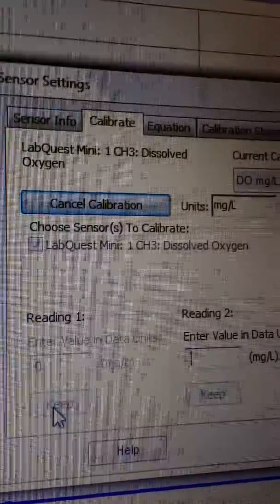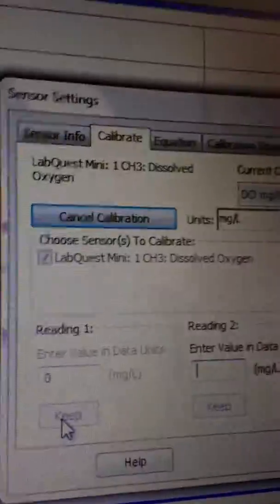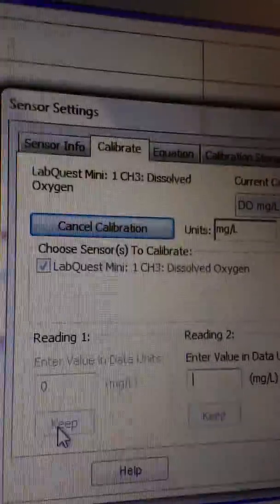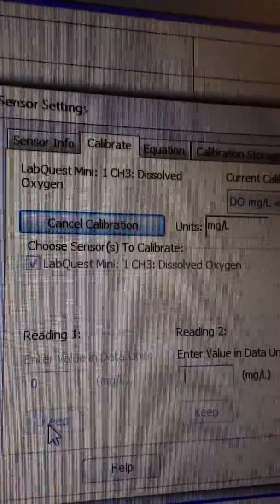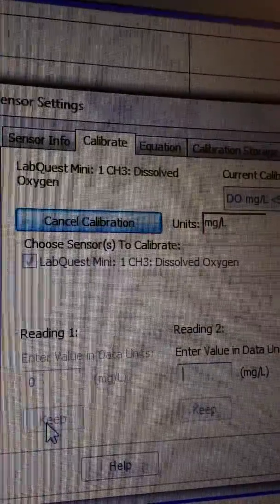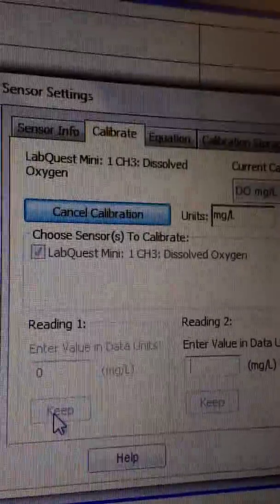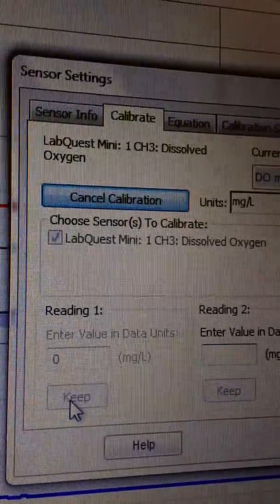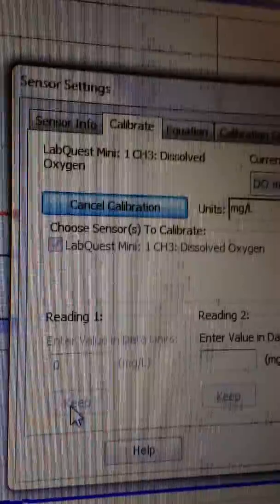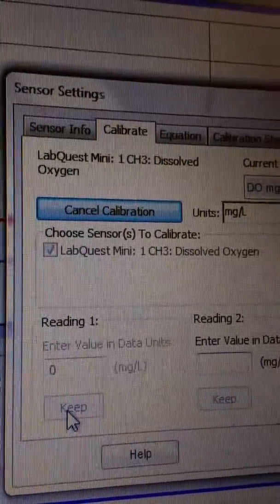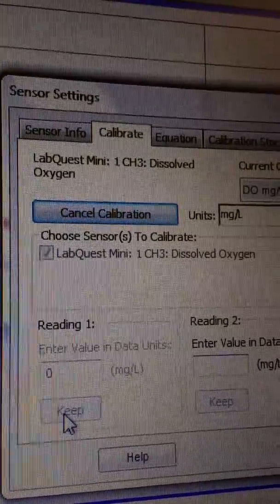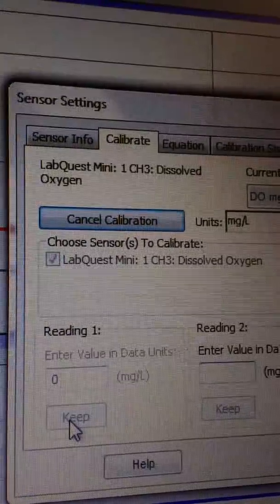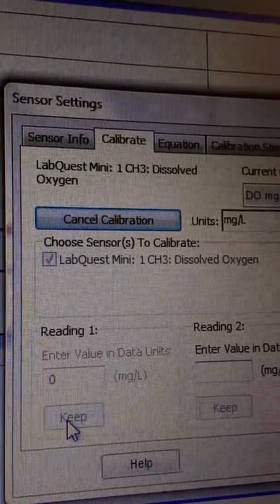Can you change reading now? No, you can't change it. It has to be within a certain range. It has to be between 0.2 and 0.5. Okay. And so right now it's 0.5. So I hit keep when it was 0.53, right? Exactly. That's fine. It's okay. Now type 0 in the known value in milligrams per liter in the edit box. When the displayed voltage for reading 1 stabilizes, click keep. You've done that? Yeah, I did that.